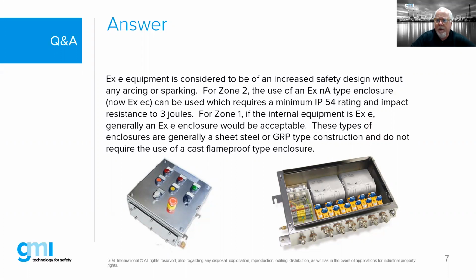So what you see there on the right-hand side is things like power supplies or relays or barriers or various other components that will have, in many cases, their own certification. So generally, when we're talking about Ex e type construction, the individual components that we put on the inside of that enclosure must all be certified. So that's one benefit of going with Ex d, that we can use general purpose equipment within Ex d and put it in a hazardous location. If we go with Ex e, then we have to make sure that all of those individual components have their own Ex certification.